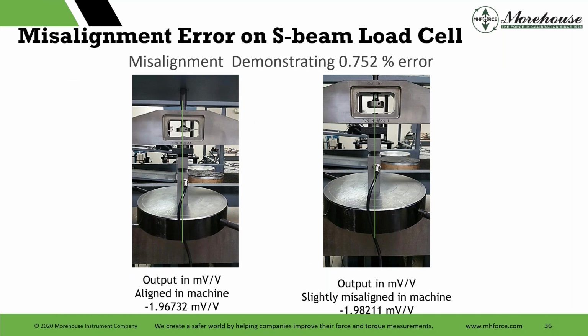Misalignment, just some things to be aware of. Say Morehouse calibrated your stuff. We got really good results because we centered everything, and then maybe a technician goes out in the field and doesn't pay attention to centering or uses a different machine, and all of a sudden the numbers do not look like they should. This is just a really bad load cell, and that's why I put it here, because the lines are there. The load cell looks pretty aligned in both pictures, but if you examine them, this one over here is a little off.